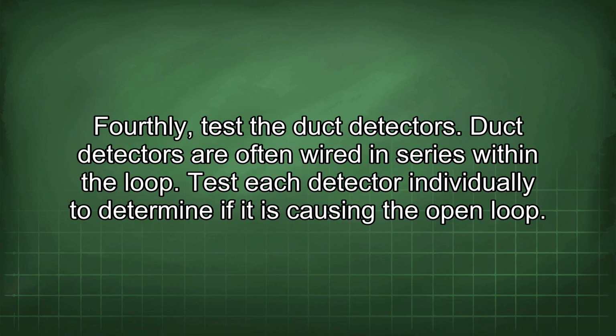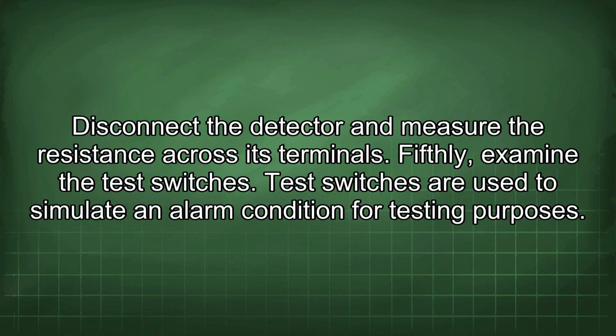Fourthly, test the duct detectors. Duct detectors are often wired in series within the loop. Test each detector individually to determine if it is causing the open loop. Disconnect the detector and measure the resistance across its terminals.